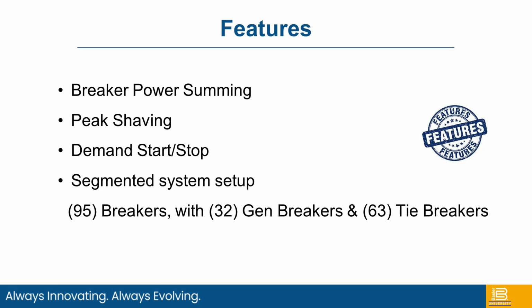Breaker power summing, so this allows us to be able to look at multiple breakers and figuring out which way the power is moving. It's a pretty important feature sometimes when you're paralleling the utility. We offer both peak shaving, base loading, demand start and stop, which demand start and stop means you can have multiple generators and they'll actually sequence themselves on and off as the loads demand.